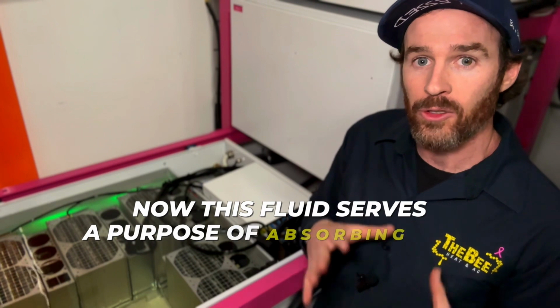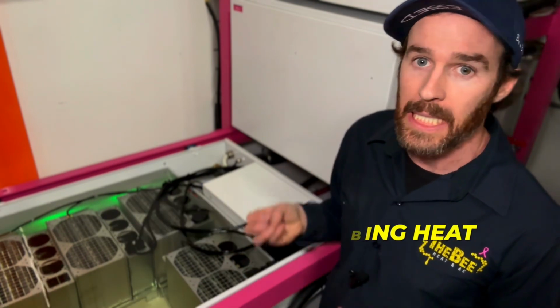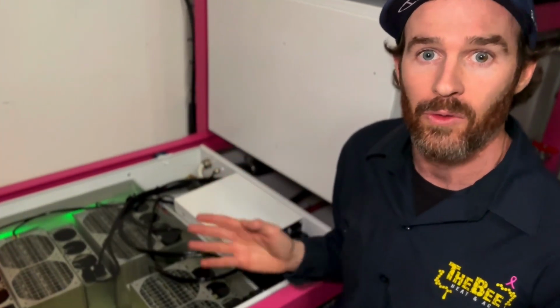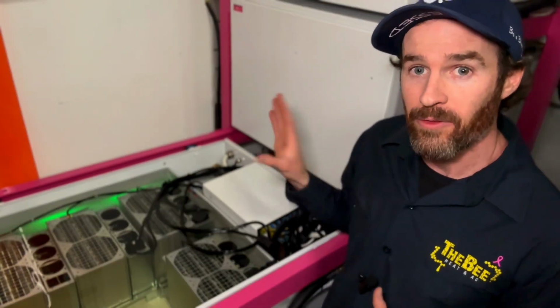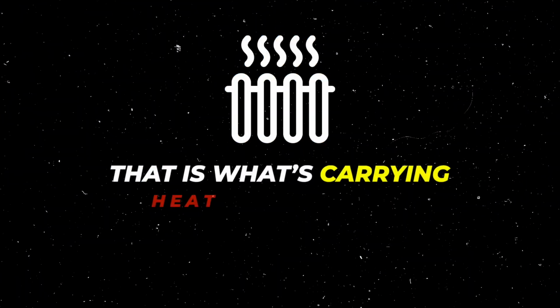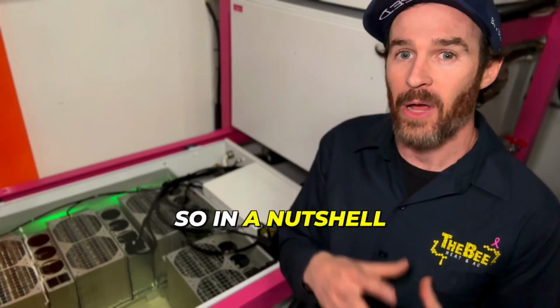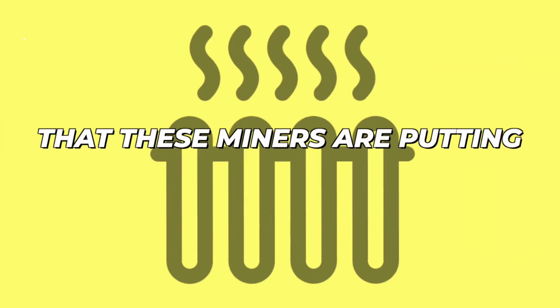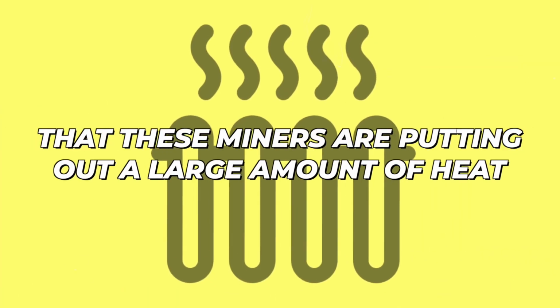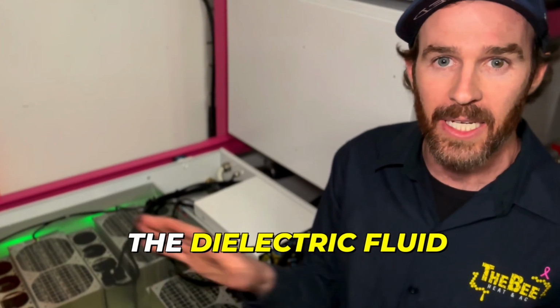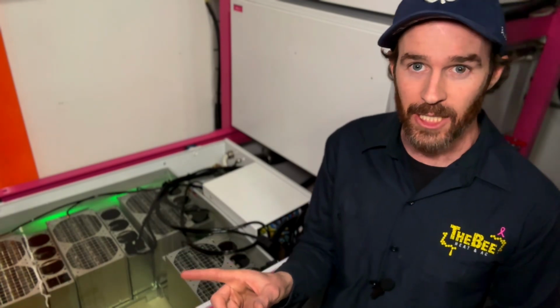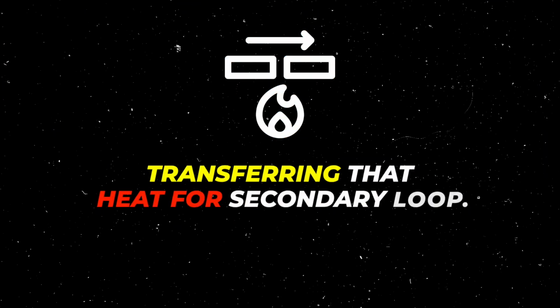This fluid serves the purpose of absorbing heat. It's circulated through a flat plate heat exchanger, just like the one I showed you, and the fluid on the secondary loop of that exchanger is our hydronics loop, which carries heat to the office. In a nutshell, the miners put out a large amount of heat, which is absorbed by the dielectric fluid, and that fluid circulates to the flat plate heat exchanger and transfers the heat to our secondary loop.